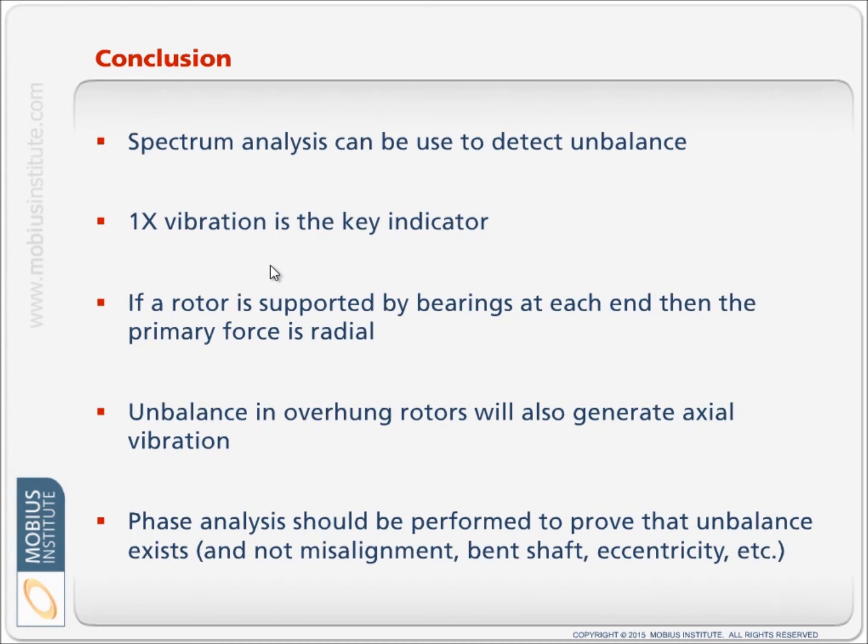Phase can help us ensure that it's unbalanced, not something else, and we can then figure out how to do the balancing job. So we can look for that 90-degree phase relationship and we can compare the vibration at either end.